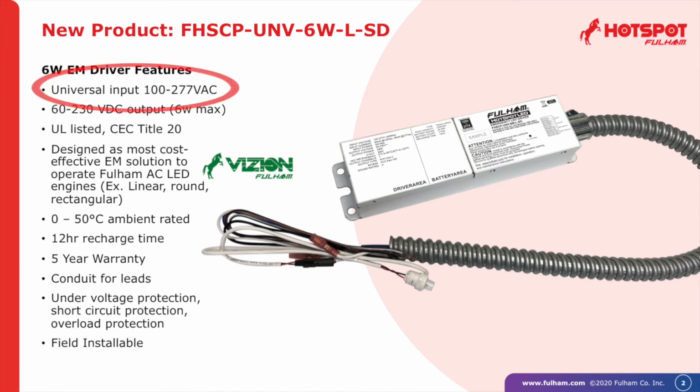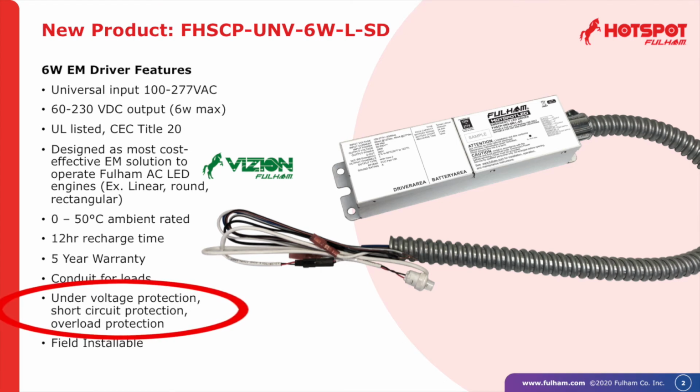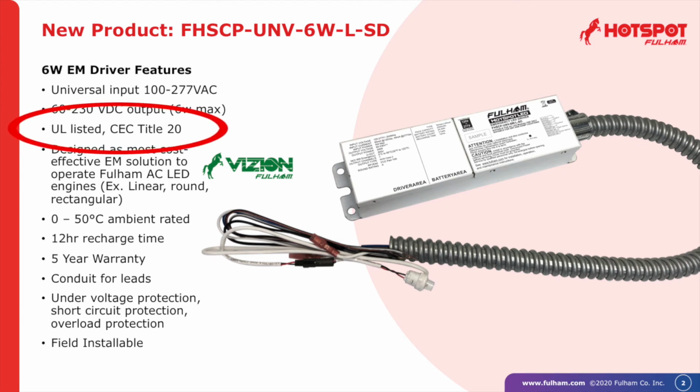It has universal input between 100 and 277 volts AC, universal output between 60 and 230 volts DC. This unique product has undervoltage protection, short circuit protection, and overload protection. It is UL classified for easy installation and meets CEC Title 20 requirements.